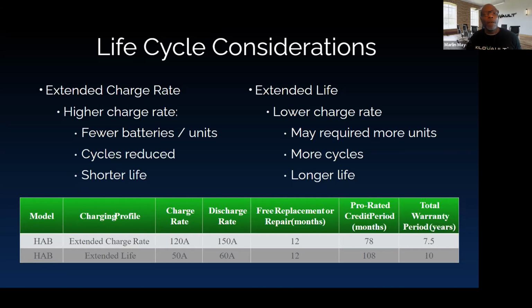We have a question from Kurt asking if the overvoltage alarm comes on with the HAB, will the HAB turn off at some point? If the overvoltage alarm comes on, the battery will actually shut off charging. The BMS will not allow the battery to charge anymore. Then when the next discharge cycle starts, if that battery is higher than the others in the bank, it will start to discharge that one, bringing it down to the others, and then they will all start to discharge together. That's where the balancing between the batteries takes place as the bank charges and discharges.